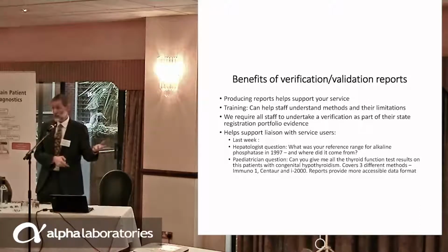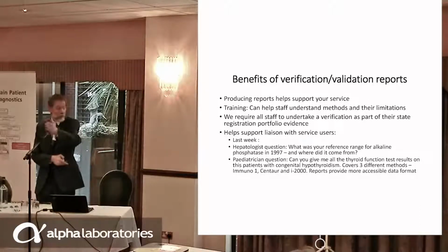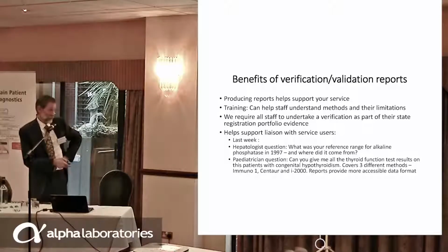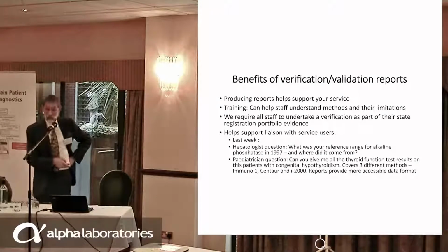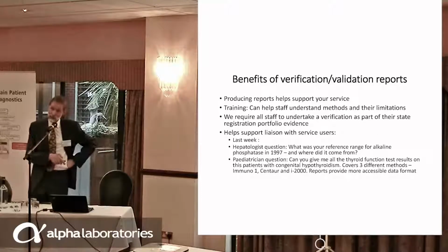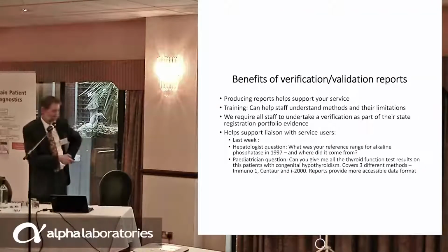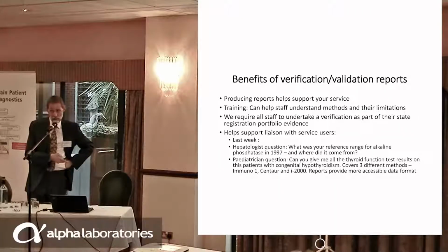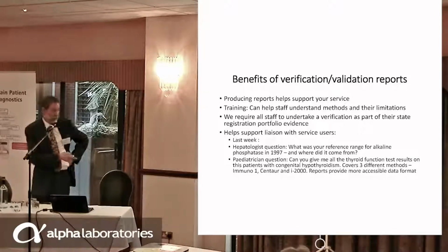Also, a paediatrician asked us to pull some data on patients with congenital hypothyroidism, and it dates back to 1999. During that time you will have seen several method changes, and we saw three method changes during that period. Each time you transition to a new method, there's going to be a difference. So if you're looking at longitudinal monitoring, how much do you take that into consideration when you're looking at that data? I think if you've got your verification reports available, you'll be able to pull that out.